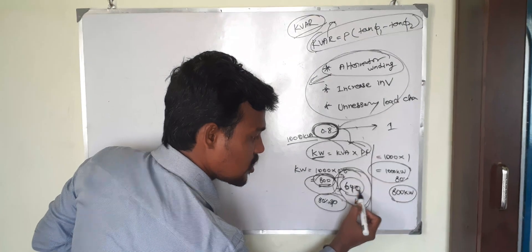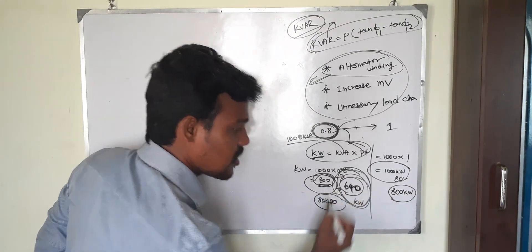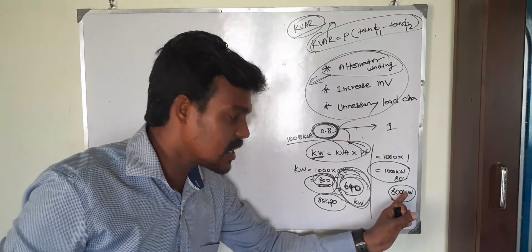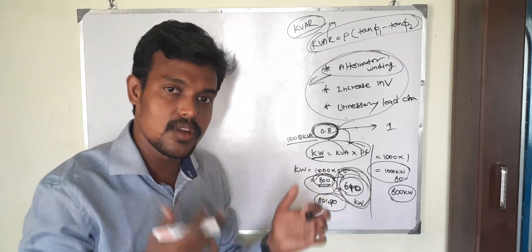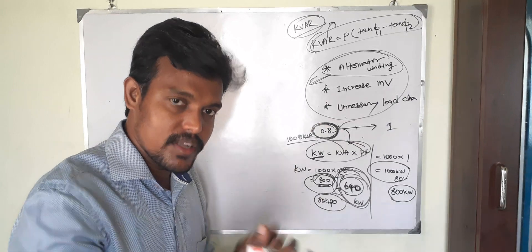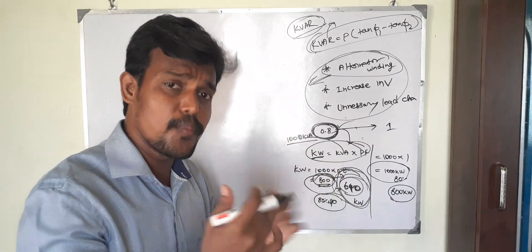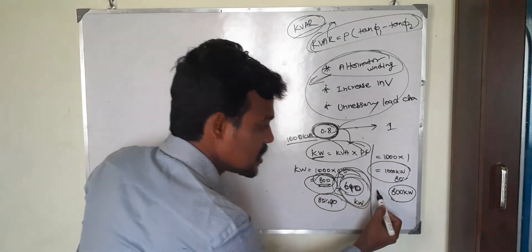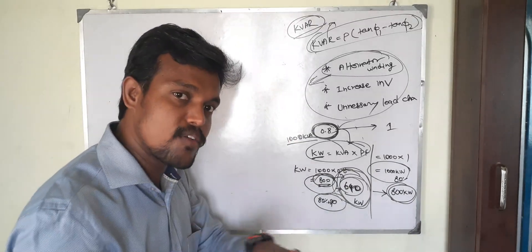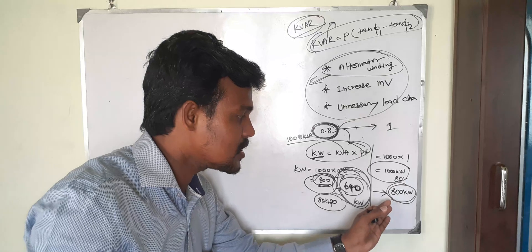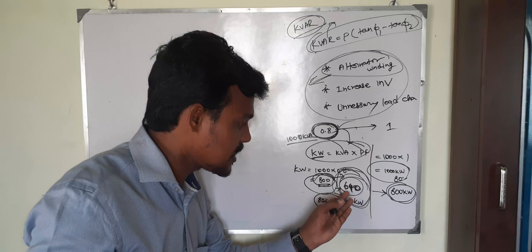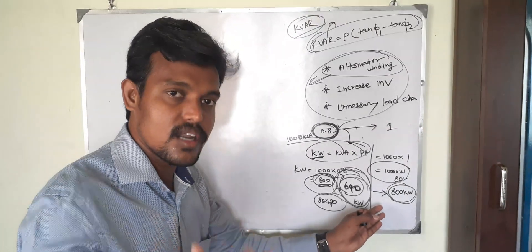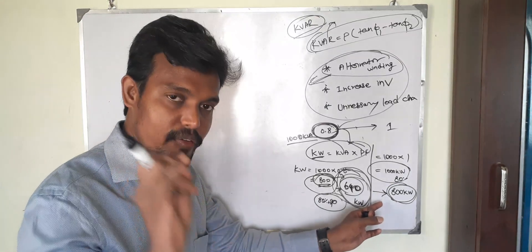At 80% load with unity power factor, the load comes to around 800 kW. But the DG is only designed to cater for 640 kW. If all the protection systems fail and the load increases to 800 kW, the alternator winding will get damaged because it is designed to cater for only 640 kW. This is the first reason we must switch off the power factor panel when the DG is running.